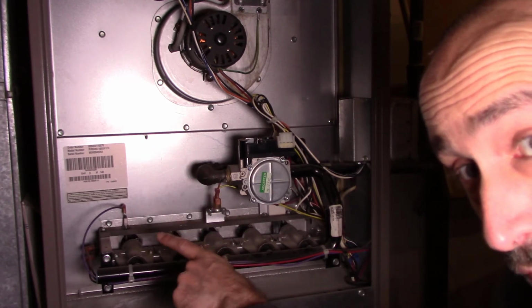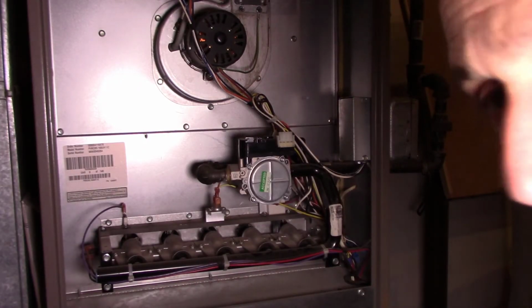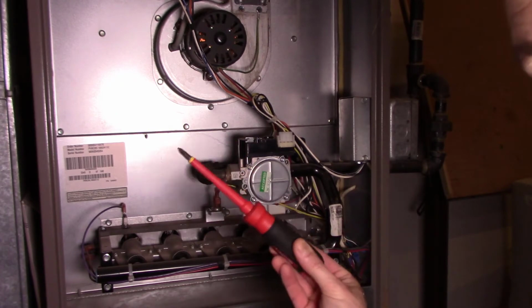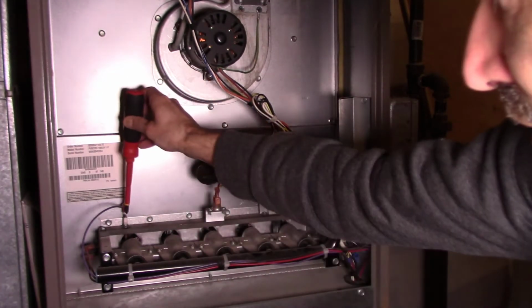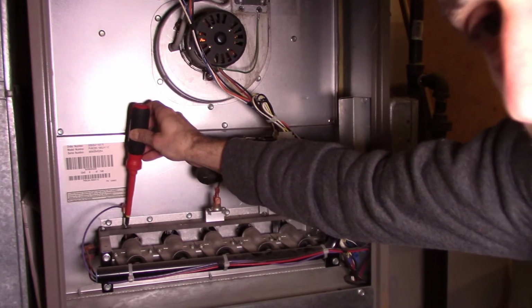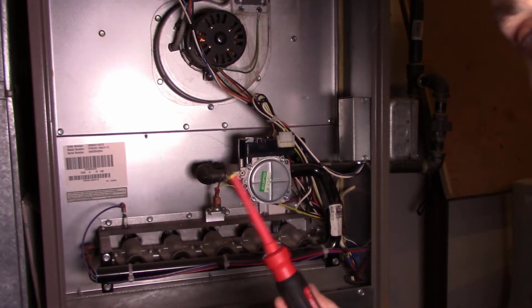So the next thing we're going to do right now is clean that. To clean the flame sensor, it's actually pretty easy. You need just, in my case, a Phillips head screwdriver, because there's just a Phillips head screw holding this thing on, or maybe a 1/4-inch nut driver.